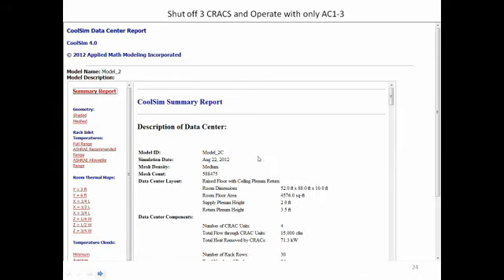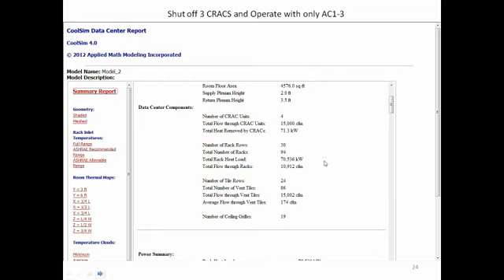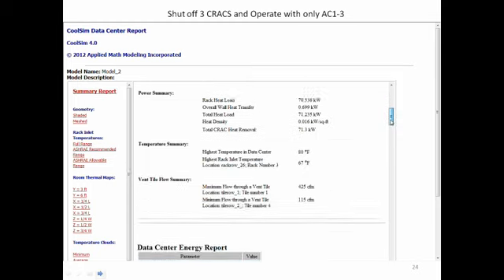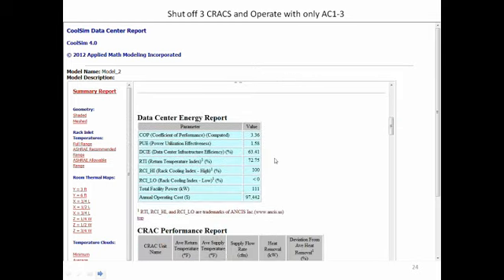So if we look at our summary report now, we'll find that the total heat load is still the same, but the flow rate is 15,000 compared to the 10 that we need. So naturally, when we go down and look at our RTI, it's going to be much better. RTI now is 72%. So it's moved from 18 to 72. We still have no problems with heat. Of course, we're running it at 55 degrees, which is a lot of the reason why. Our COP has improved to 3.36.